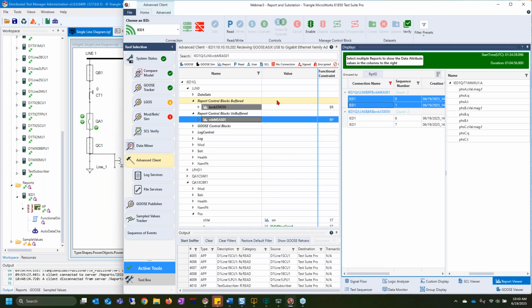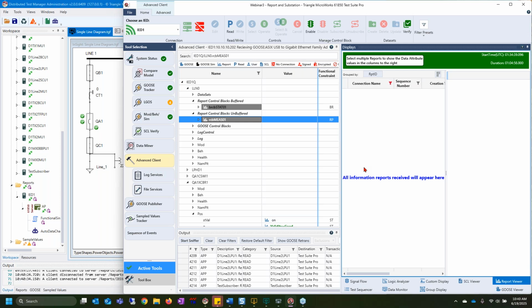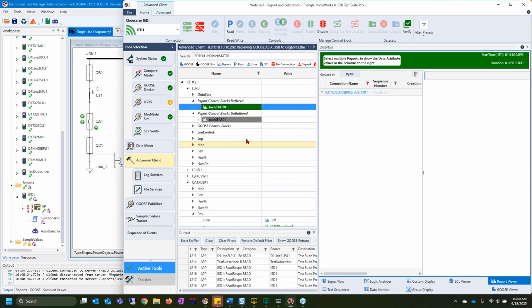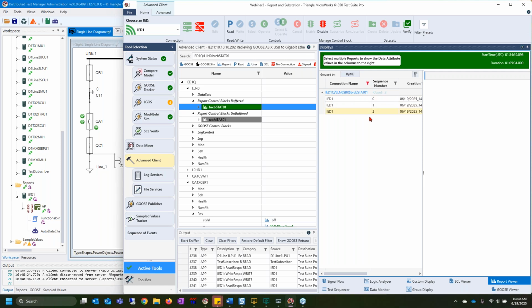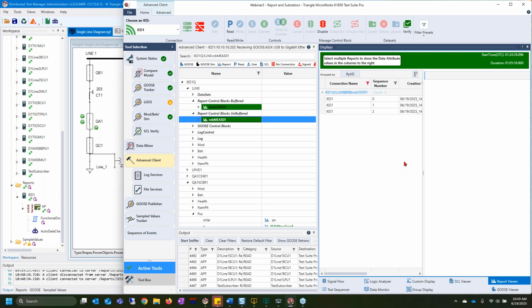And again, I can just toggle this breaker a few times. And when I connect back up, I'll clear this out to make it more obvious. If I enable this report, we'll see that we got the 3 messages that happened while I was offline. The 3 reports still came across. But when I enable the measurements report control block, we aren't getting anything until the actual value changes while we have that enabled. So that's realistically what the reports look like between buffered, unbuffered, and polling.